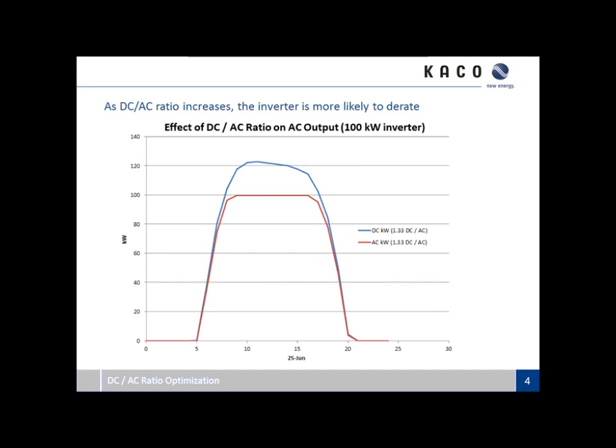This is a quick look at DC to AC ratio and the impact it has on energy production. In this case, it's a ratio of 1.33 — 133 kilowatts DC to a 100 kilowatt AC inverter. This is time series data pulled from SAM on a given day in June in New Mexico. You can see that on this given day, the array wants to put out about 125 kilowatts. From 10 a.m. to 4 p.m., the inverter is stepping off its maximum power point and throttling back — not able to process all of the available DC power. Some people look at this and say you're throwing away energy, which is true — you're not utilizing all of the array's potential.